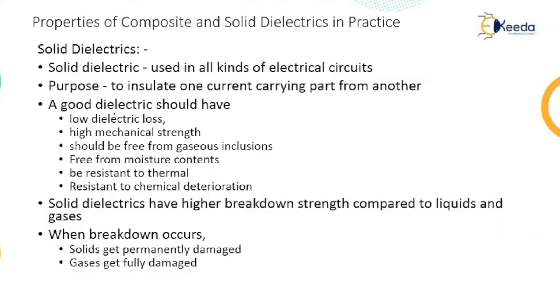A dielectric is best suitable when its dielectric loss is low, when it has high mechanical strength, when the solid insulating material is free from air or gas pockets — because gas pockets reduce the strength — and it must be free from moisture contents, as moisture reduces both the electrical and mechanical properties and overall breakdown strength.